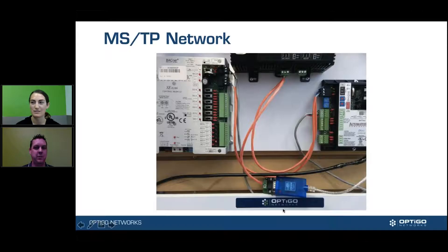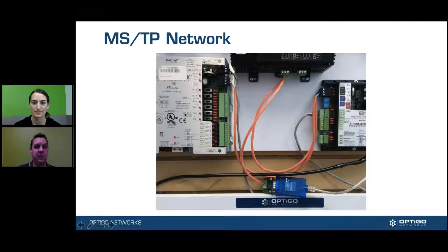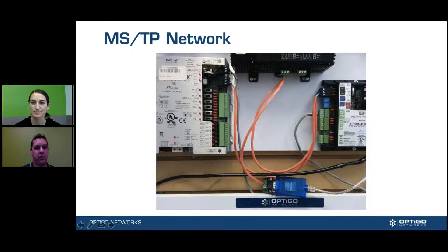Most MSTP networks always have a certain level of issues. Very rarely do you install one without a couple of issues. Typically what you have is a physical wiring problem — bad wiring or bad terminations. Possibly you have a device issue, an actual controller issue, but that's rare. You also have bad configurations for MSTP settings, but typically what you're focusing on is wiring problems.